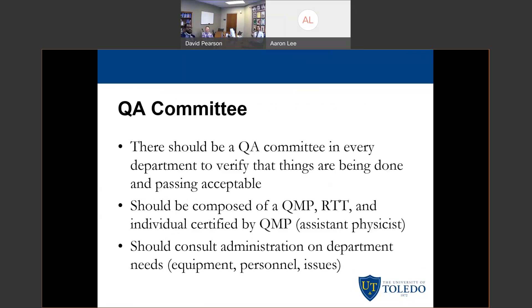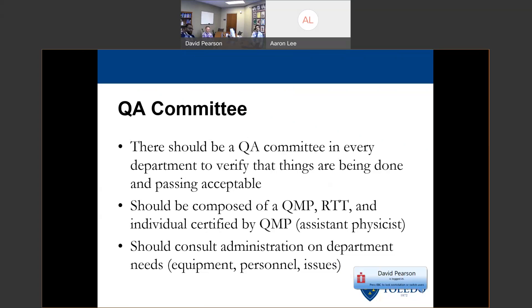Getting towards the end, they also talk about how every department should have a QA committee that meets regularly. This QA committee should be composed of a QMP, a radiation therapist who is actually performing daily QA regularly, and an individual certified by the QMP — this could be an assistant physicist, a resident, or a student doing a significant amount of monthly or weekly QA, and does not necessarily need to be board certified. This committee should make sure things are going smoothly, that there are no consistent issues, that QA is being done, and should bring up new QA procedures if something needs to be changed. They should also consult administration on personnel issues — such as when commissioning a new machine without having hired anyone — and bring up requests for new QA devices through this committee.